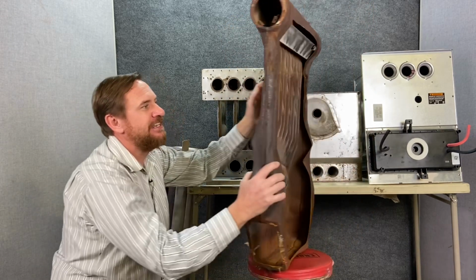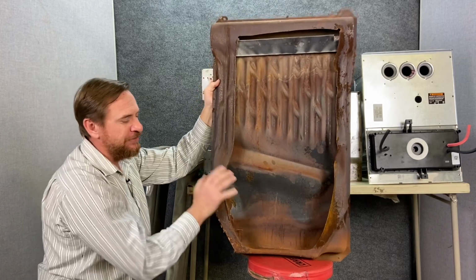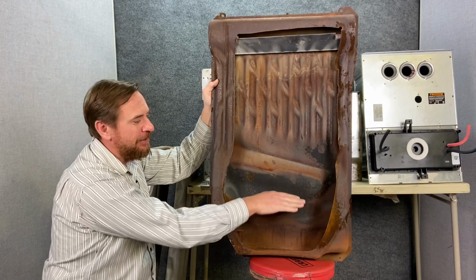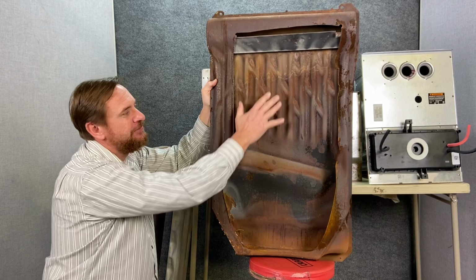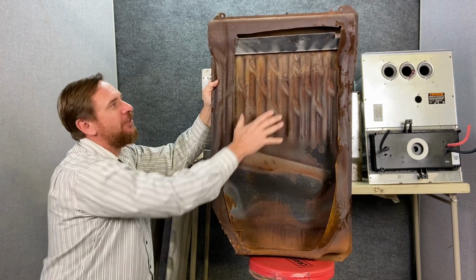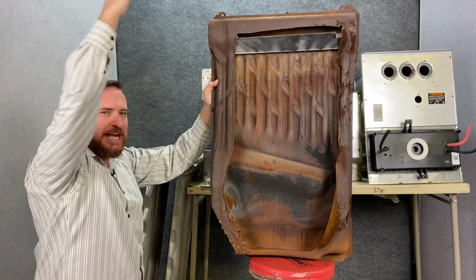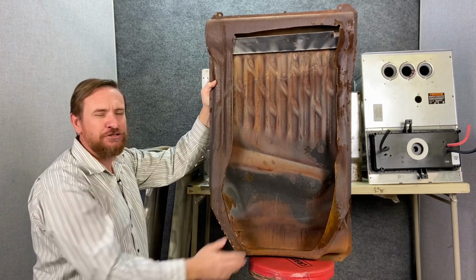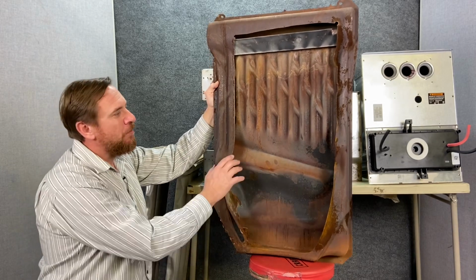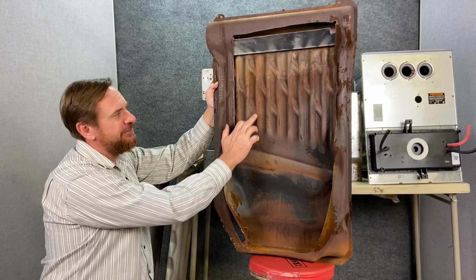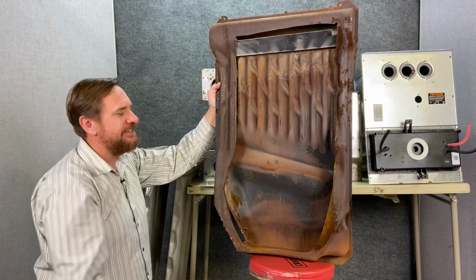So on this side of the heat exchanger, I have it cut open. So the flames, the burners would be here burning up, and then all of this was still going to be hot gases. All the hot gases collect at the top and it naturally drafts out. So this is a natural draft heat exchanger. One of the things we look for is rust. There's a significant amount of rust in this heat exchanger.